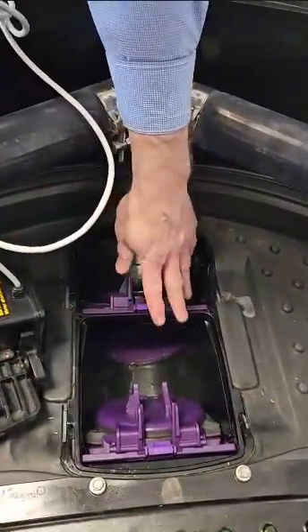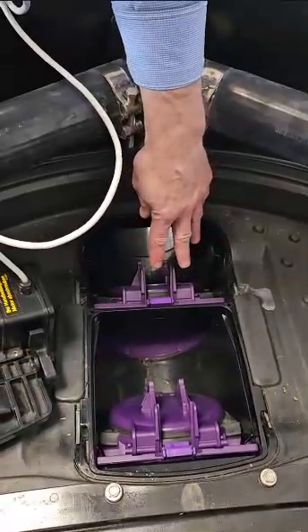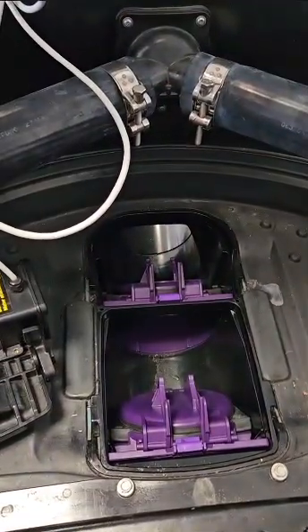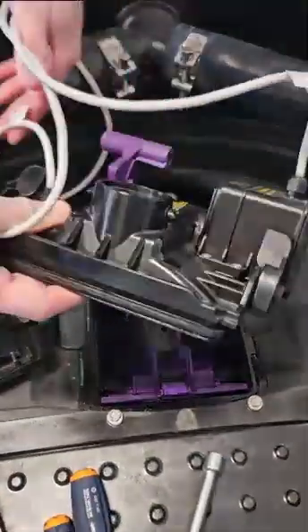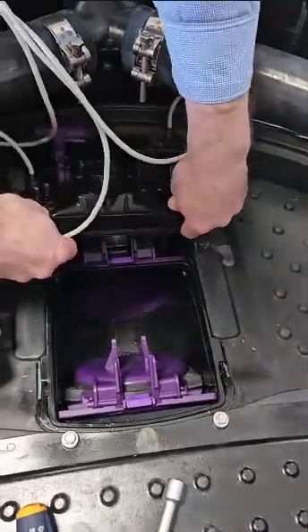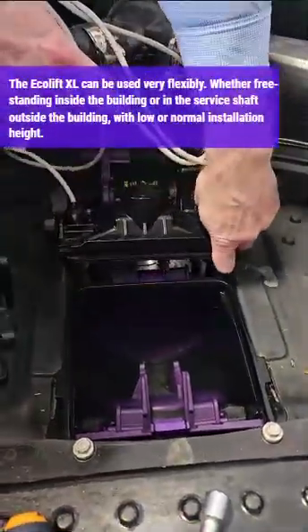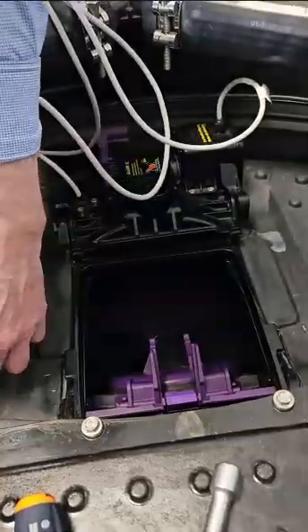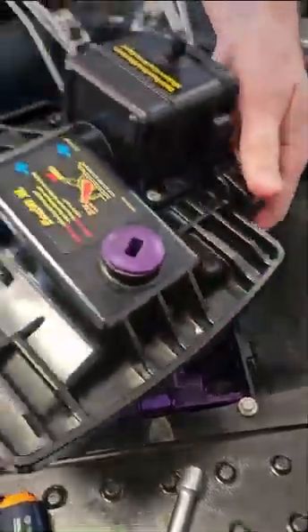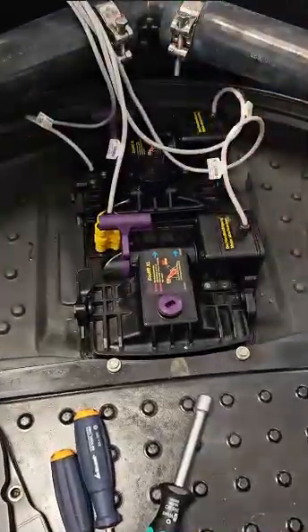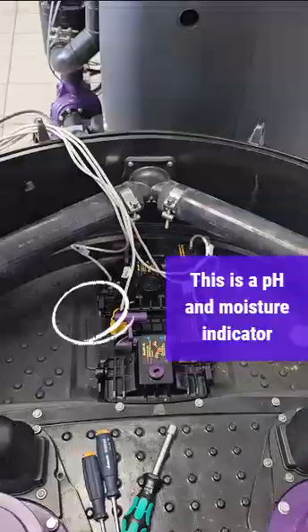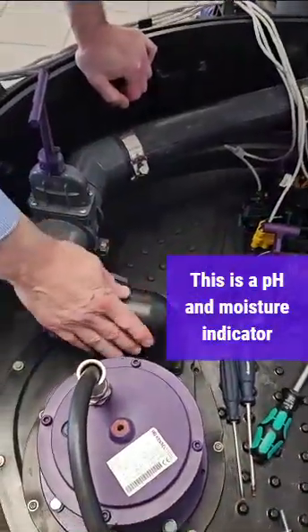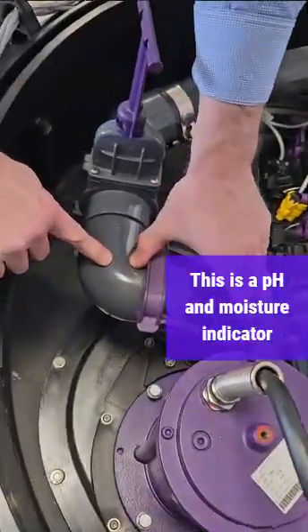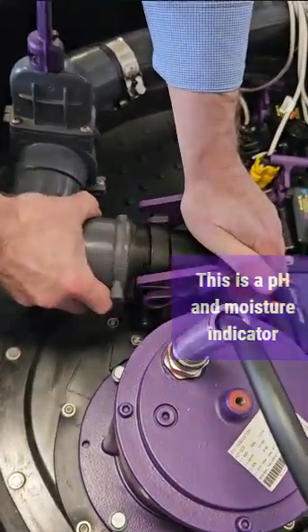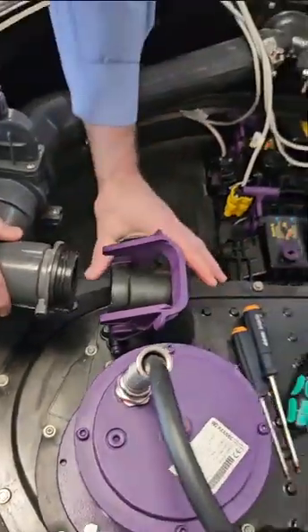I'll put this housing back in, as well as this flap back on. Here's the flap connector. And now we have the same thing up front. Again, the same 2 finger levers to open up and prop open this cover. Here we see the second cover, also with a second motor and also optical probe. If you have an optical probe with this little small white piece of litmus paper, not all probes have them. If you do, this should be white. If it's a different color, blue or dark colored or black, that means there's moisture inside the probe and you should consider replacing the probe.